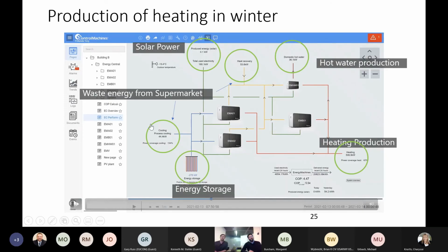So what goes on is - this is a high-level pseudo P&ID diagram of our system. You see we have the heat pumps here in the middle. We have two base load heat pumps that basically chill the cold system and deliver heating for the building. Then we have a top load heat pump, which produces the hot water via this unit up here, and can also assist in peak load situations on the space heating system.